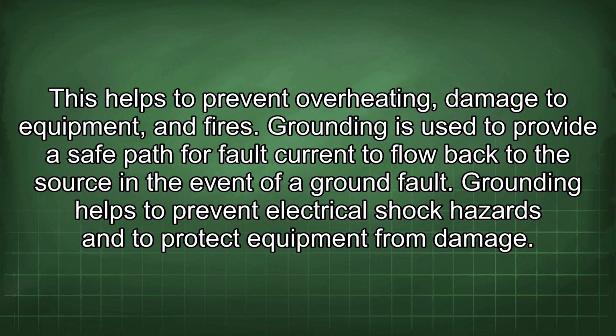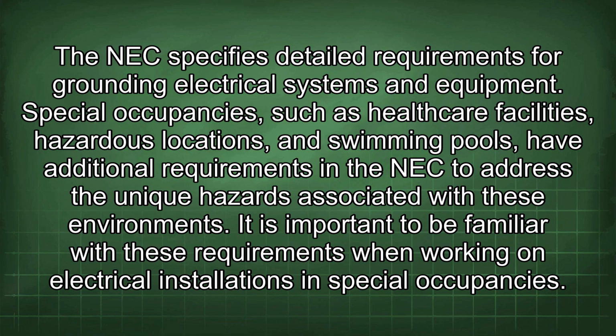Grounding is used to provide a safe path for fault current to flow back to the source in the event of a ground fault. Grounding helps to prevent electrical shock hazards and to protect equipment from damage. The NEC specifies detailed requirements for grounding electrical systems and equipment. Special occupancies such as healthcare facilities, hazardous locations, and swimming pools have additional requirements in the NEC to address the unique hazards associated with these environments. It is important to be familiar with these requirements when working on electrical installations in special occupancies.